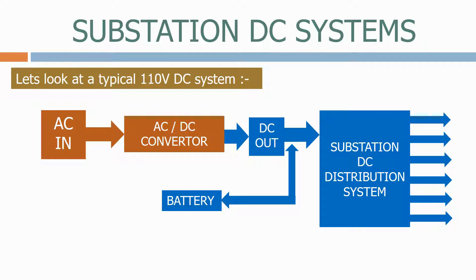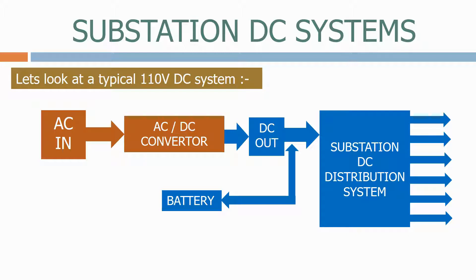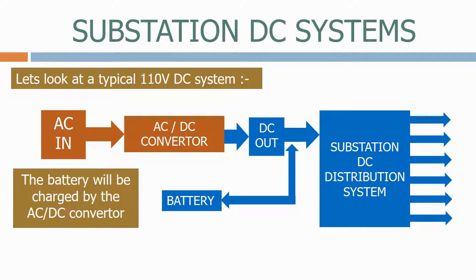In case the AC system fails, we have a backup substation battery. Under normal conditions, the battery will be charged by the AC to DC converter. The AC to DC converter therefore needs to be rated for the full DC system load and the charging current necessary for the battery.